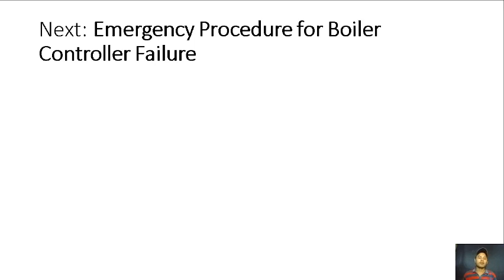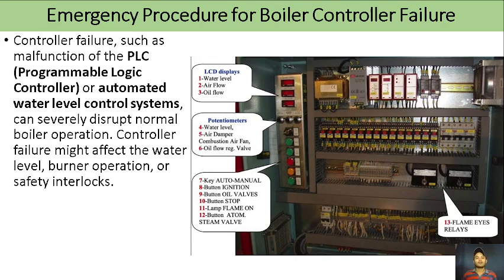Okay, next, what will we do if we have emergency procedure for controller failure in our boiler? So this is on the electrical side. So emergency procedure for boiler control failure. Controller failures such as malfunctions of the PLC or automated water level control systems can severely disrupt normal boiler operation. Controller failure might affect the water level, burner operation, or safety interlocks. So this is what's inside our control panel.